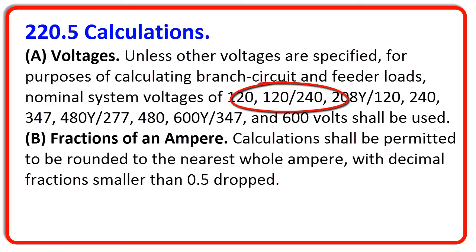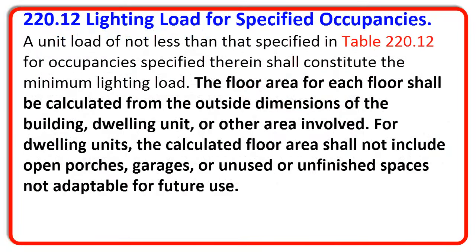So what do we use to figure our calculations with? We need to figure our lighting load for our dwelling unit. And in 220.12, it lets us know that the floor area for each floor shall be calculated from the outside dimensions of the dwelling unit. And specifically for dwelling units, when we calculate the floor area, it will not include open porches, garages, or unused or unfinished spaces that are not adaptable for future use.